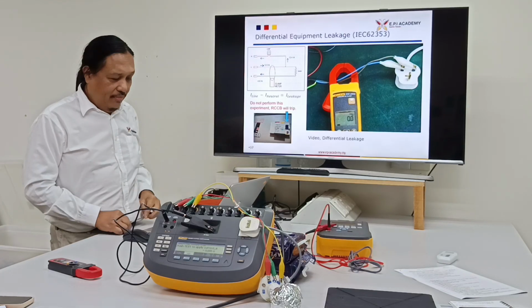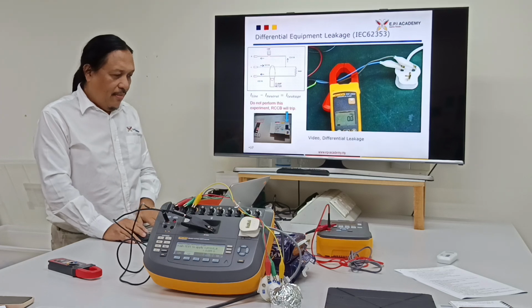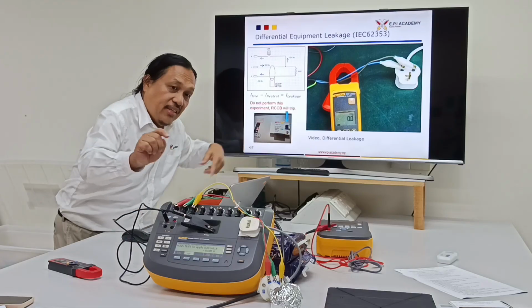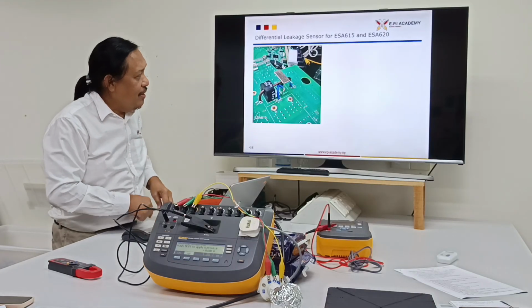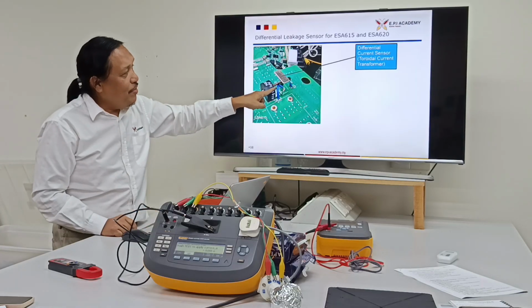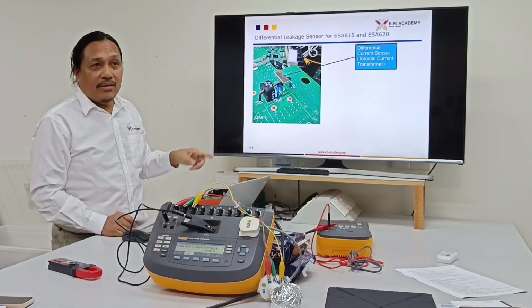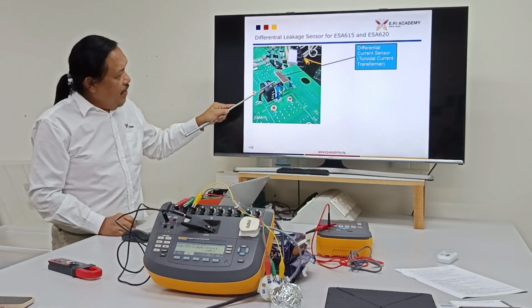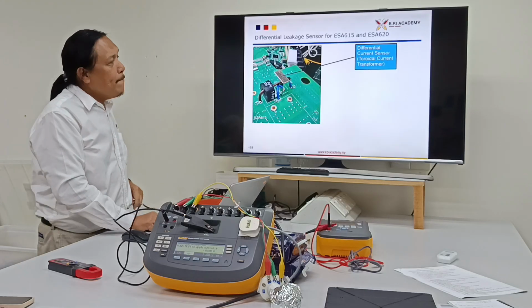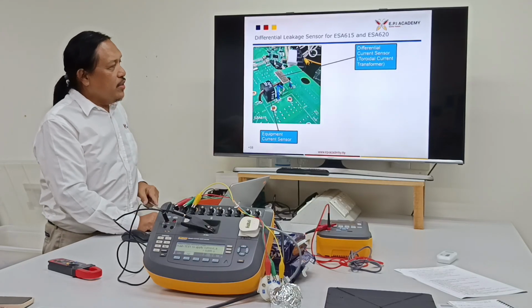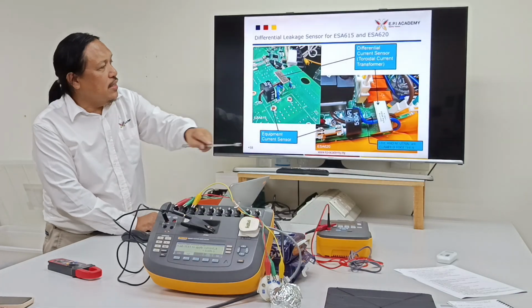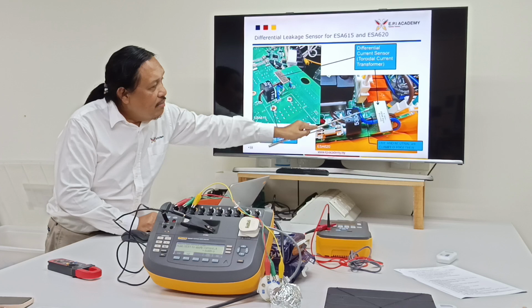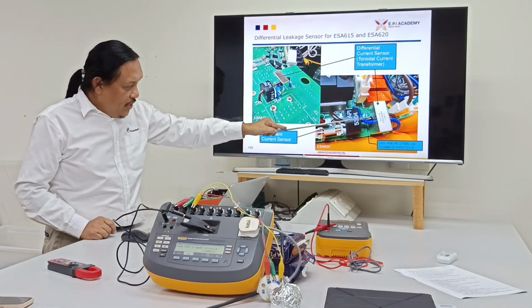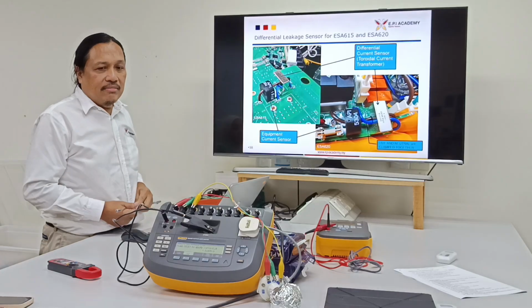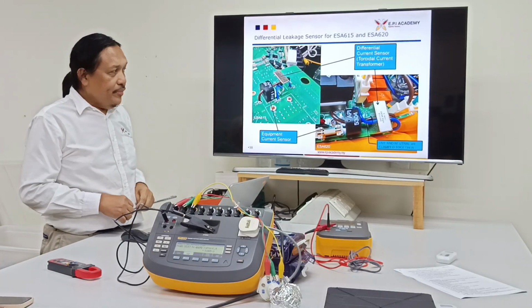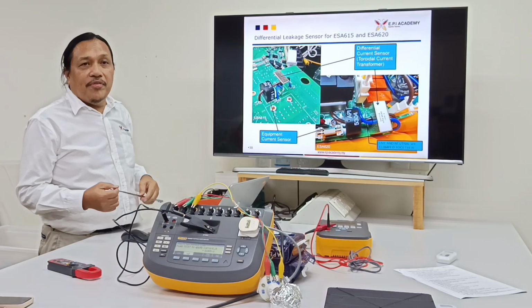Difference means subtraction. And of course, there is no clamp meter inside this. What you have is only a sensor, with live and neutral inside it, like the clamp meter. So this is the differential sensor. This is the main current sensor, for model 615, and for model 620, see that one? The differential current sensor, then live and neutral inside, like the clamp meter. So that's how it works. Differential.